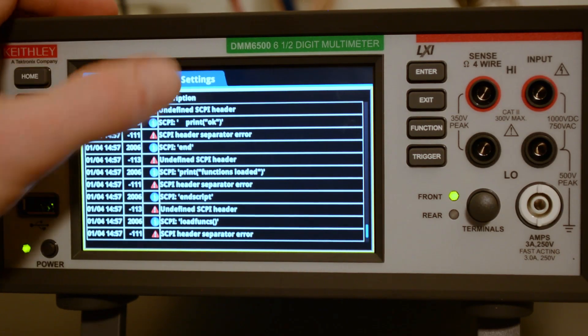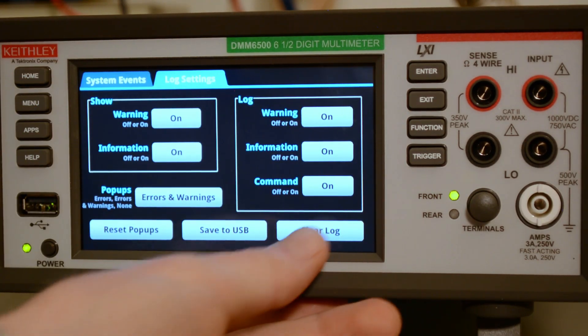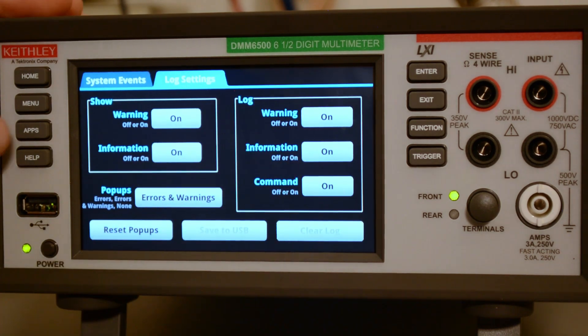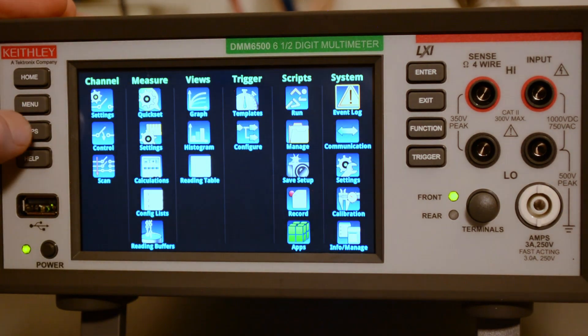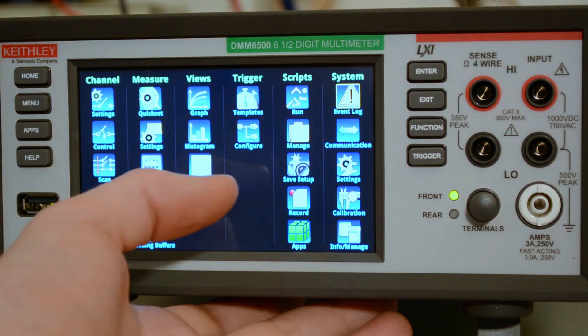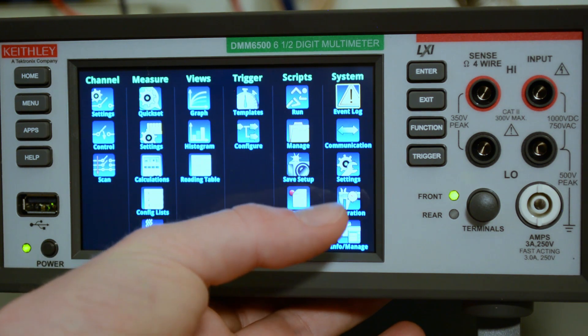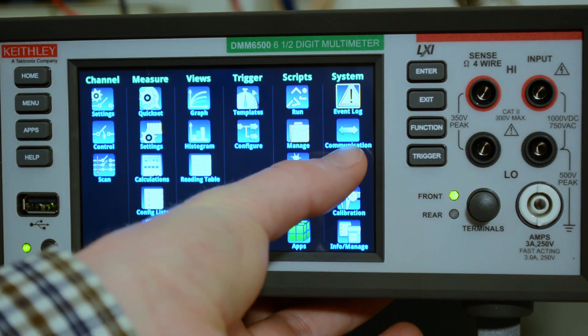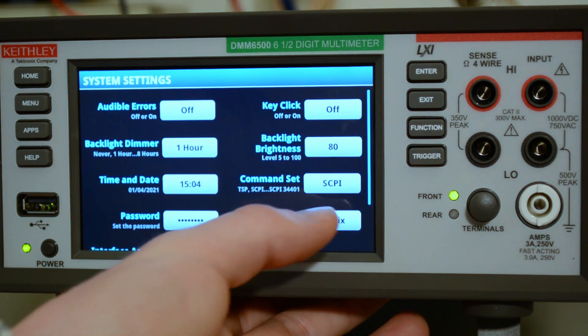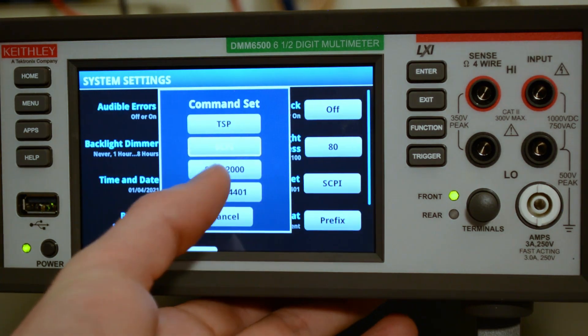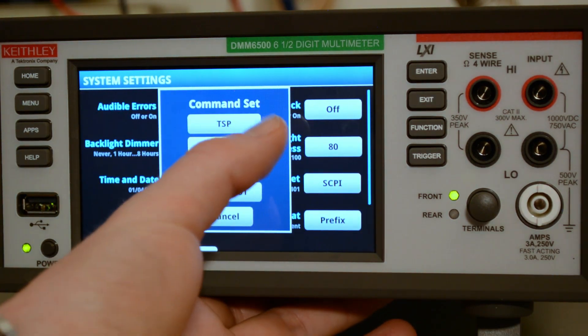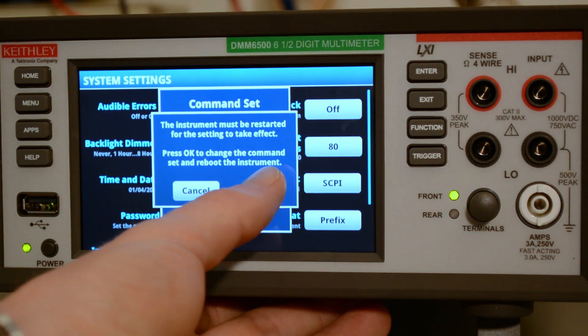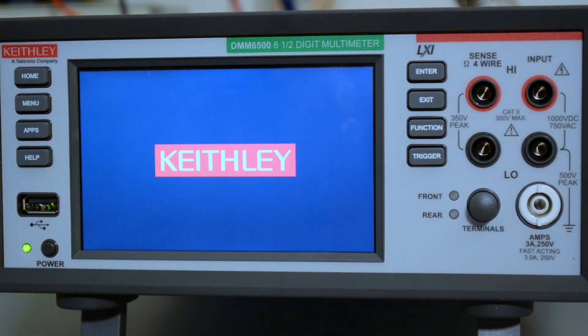So let's get rid of all these logs here. We'll clear the logs. And then back at the menu screen. So it says to change the command set, you go to settings, and then command set. So here it's on SCPI. We'll change it to TSP. OK. Now it's got to restart itself.